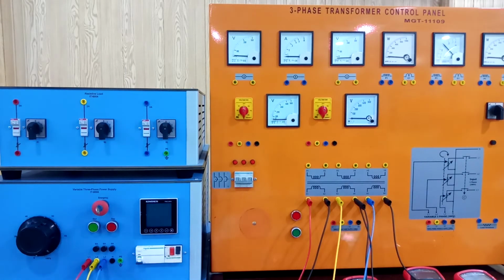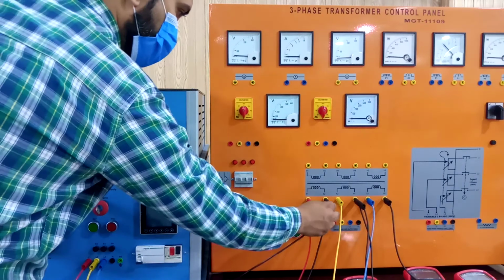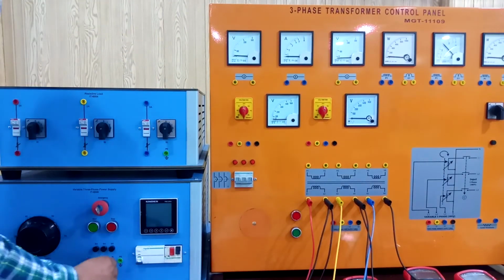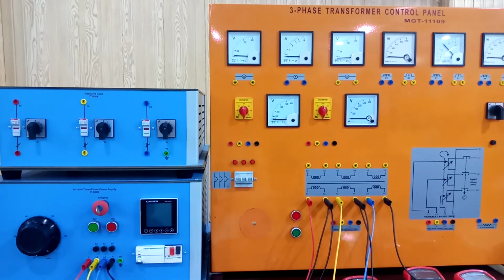Next we have to connect the neutral all the way to the neutral of the power supply, or you can say we have to connect the star point of the transformer to the neutral of the power supply. What we have to do is connect one of the transformers or one of the common connections here, so I'm just sorting out the wires. From x2 we will connect the neutral. So now our connections for the primary side, or the high voltage side, are complete, and three phases are connected to the transformer, and the neutral is also connected here.